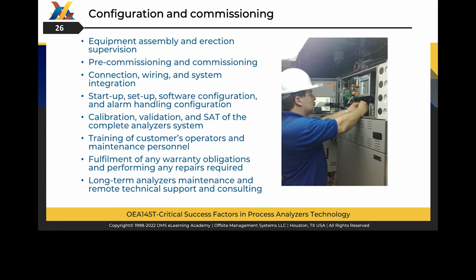Typically, the following on-site services shall be provided by system integrators after analyzer systems installation: equipment assembly and erection supervision, pre-commissioning and commissioning, connection, wiring, and system integration, startup, setup, software configuration, and alarm handling configuration, calibration, validation, and SAT of the complete analyzer system, training of customers' operators and maintenance personnel, fulfillment of any warranty obligations and performing any repairs required, and long-term analyzers maintenance and remote technical support and consulting.